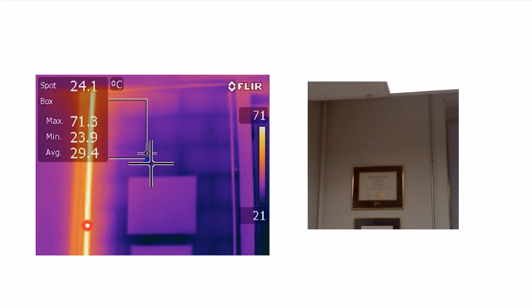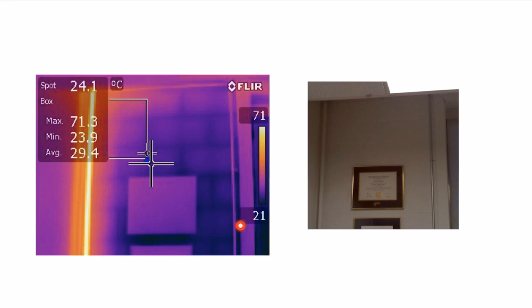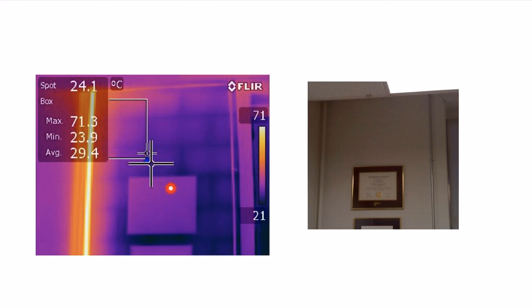This pipe, which is painted with the same paint having the same emissivity, is reading a much higher temperature. That's at the high end of our scale and very clearly this is a hot water pipe feeding the radiator underneath my desk. We're flowing hot water in there at a much higher temperature, which jumps out stunningly. This conduit here is an electrical conduit with nothing on it. That's a bare, lower emissivity material. Even though it's at the same temperature as the wall or very close to it, you're reading a higher temperature on this. That's really seeing the emissivity difference. Likewise, you're seeing an emissivity difference or reflectivity difference on the glass on that frame.